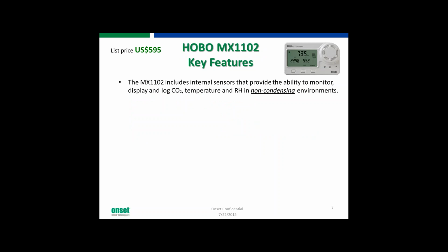It includes sensors for monitoring temperature, relative humidity, and CO2, built into the logger. They're internal to the device, and it's designed to be used in a non-condensing environment. We get a lot of questions about monitoring CO2 in greenhouses and outdoor spaces, but that's not really where this is designed, what this is designed for.